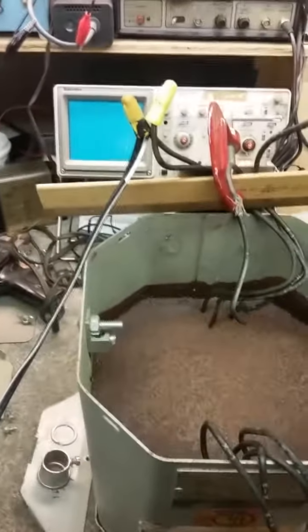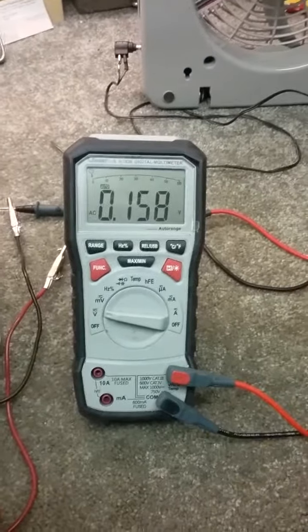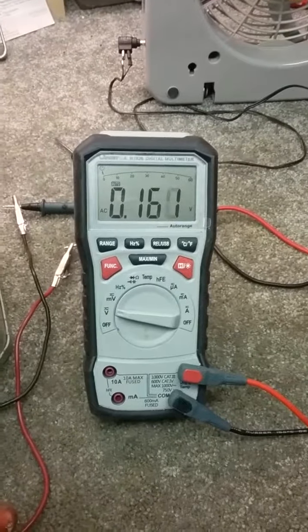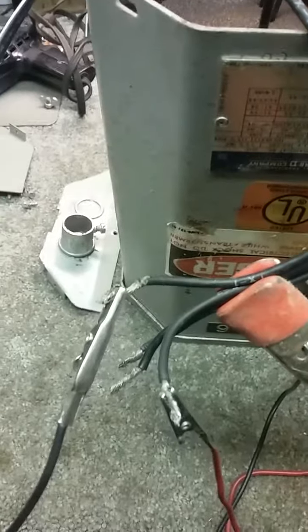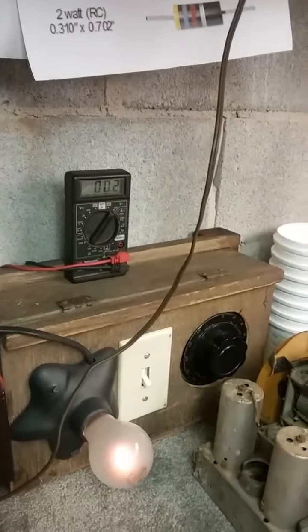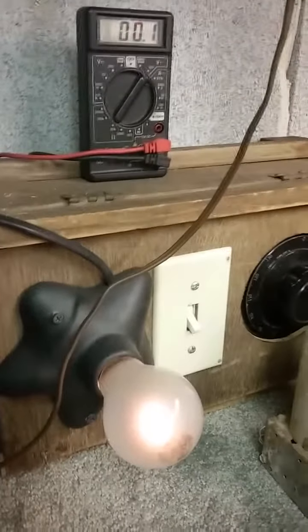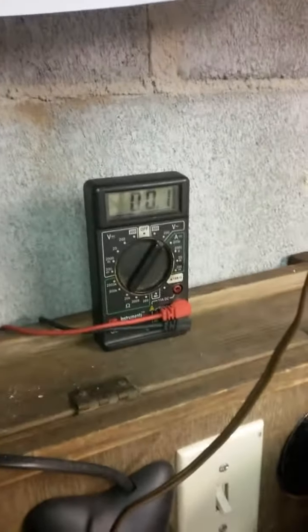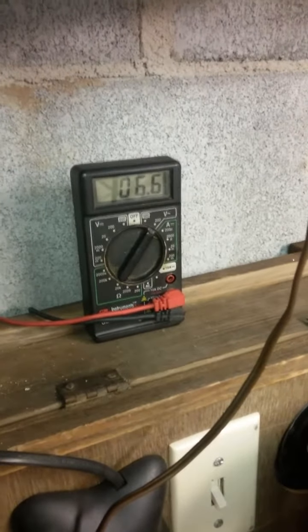Okay, I've got this system energized. This transformer now has a little bit of voltage going into the primary. I set my meter on AC volts. See, I'm at 0.16 volts on the output of this first field, and according to the meter, I'm putting in 0.2 volts. So that sounds about right. As you can see, the little light bulb is glowing because I am using the current limiting bulb. But I'm going to turn up this voltage to about 20 volts.